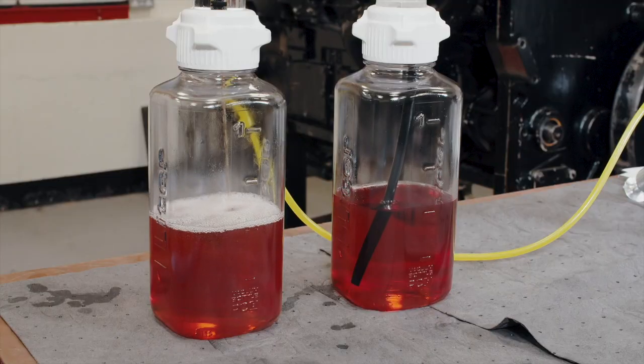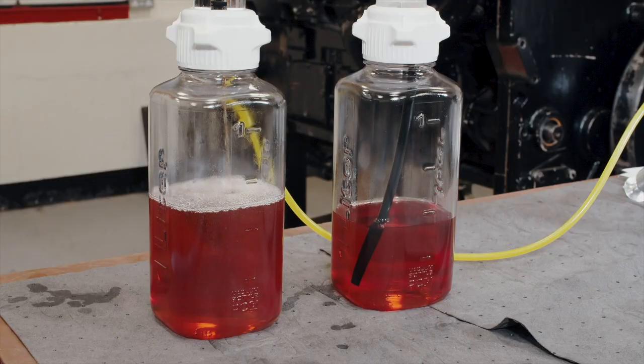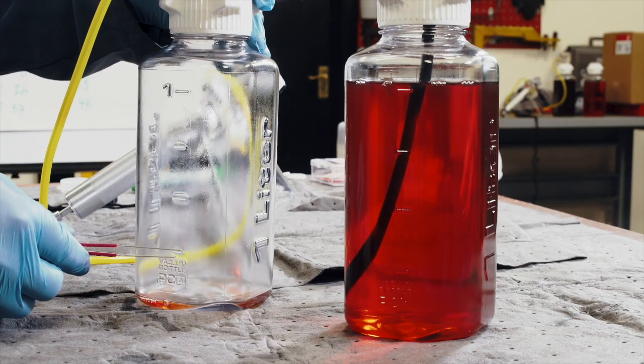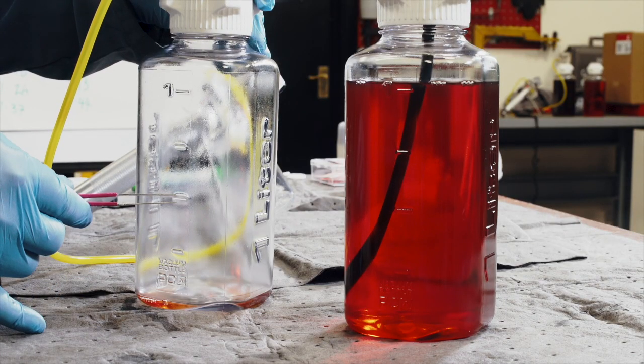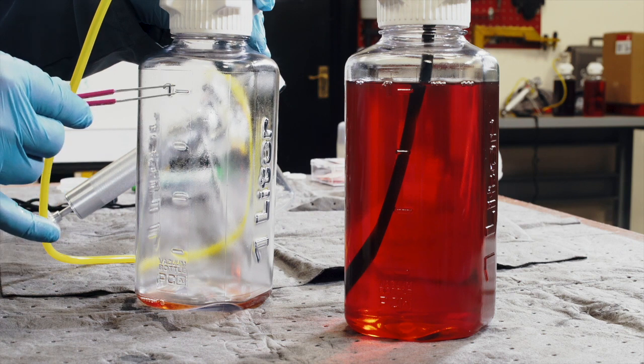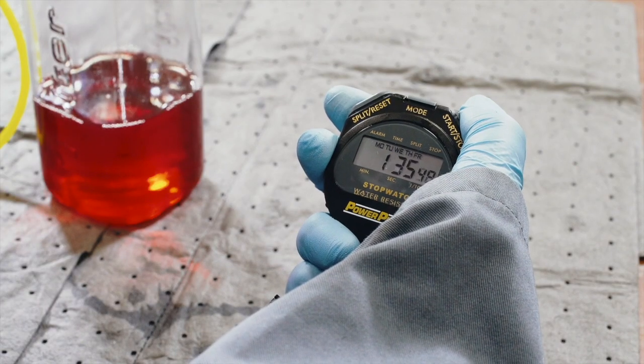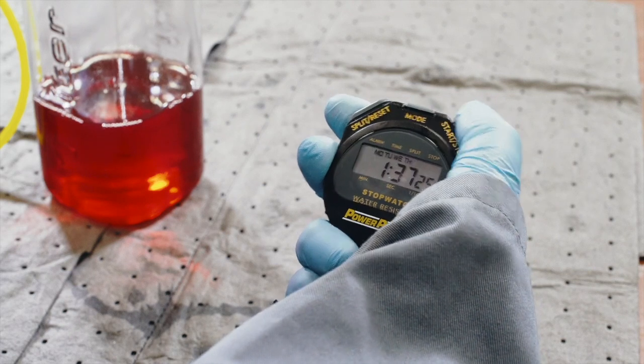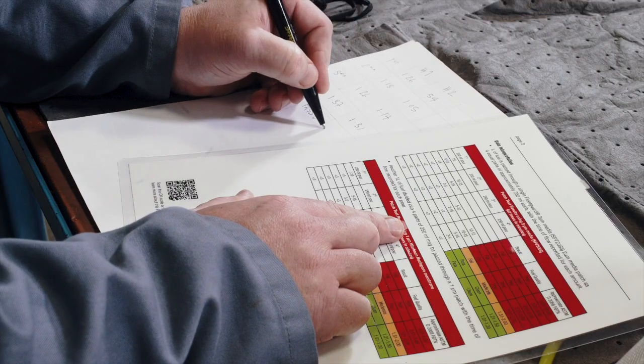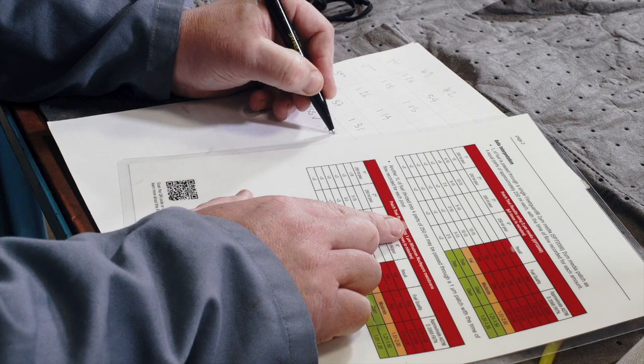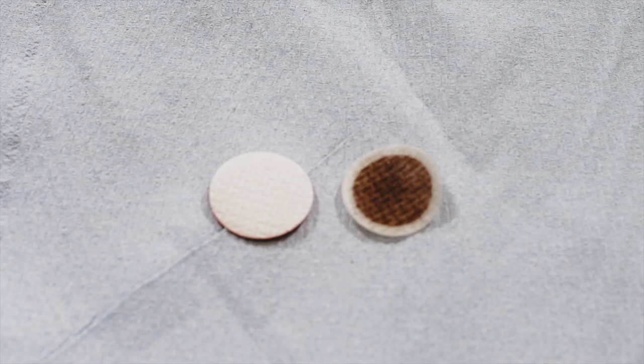The bottles are graduated and can be used to record the time as the 250 millilitre, 500 millilitre, 750 millilitre, and one litre of fuel is collected. Record each time as it passes the mark, and once you have the times, use the data interpretation card to assess the quality of fuel. You can also inspect the media used in the test.